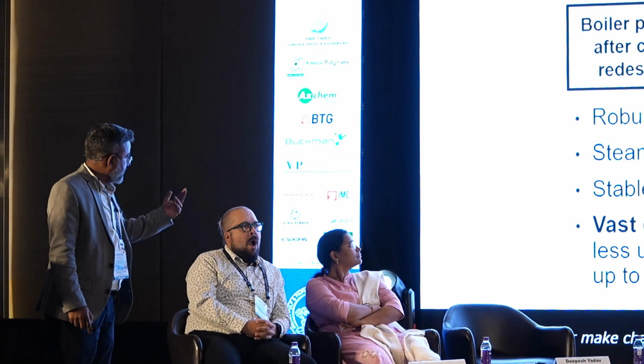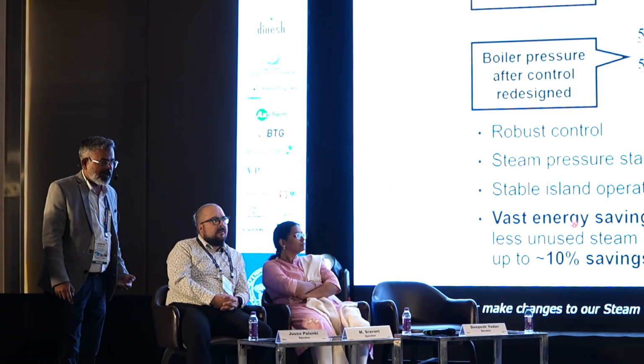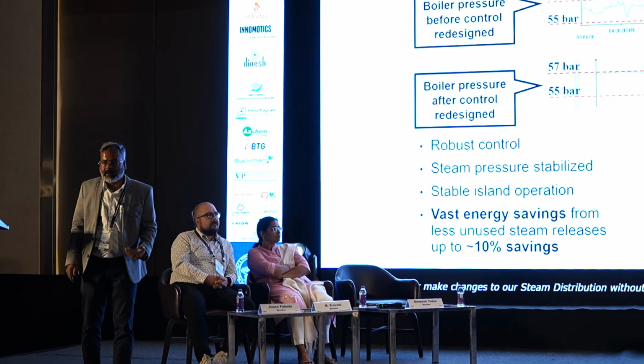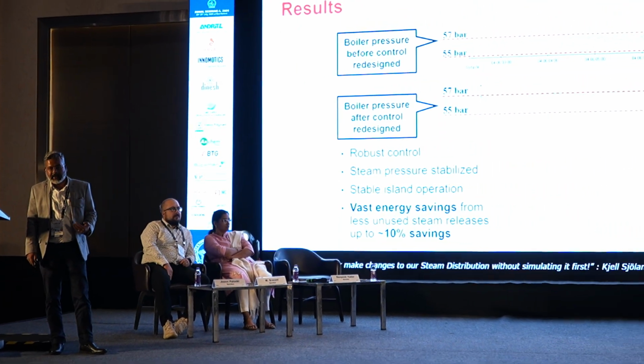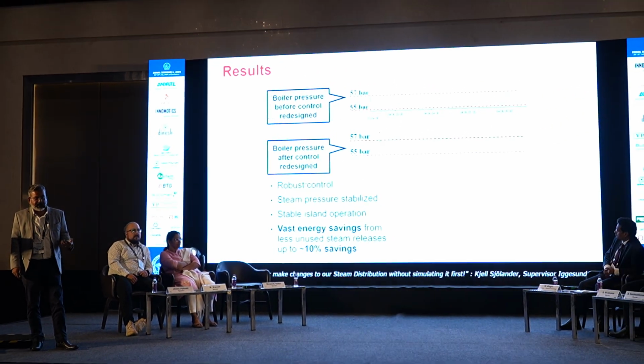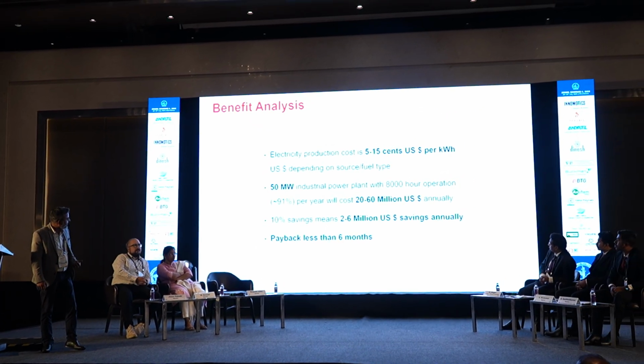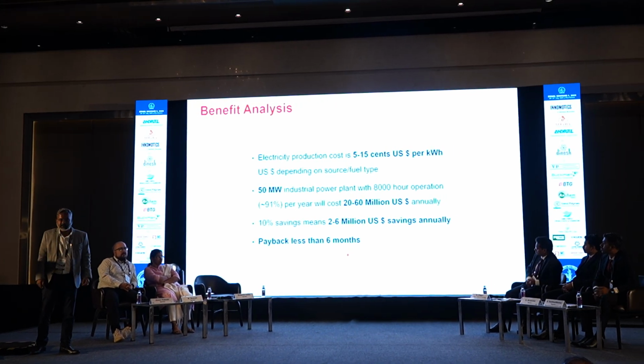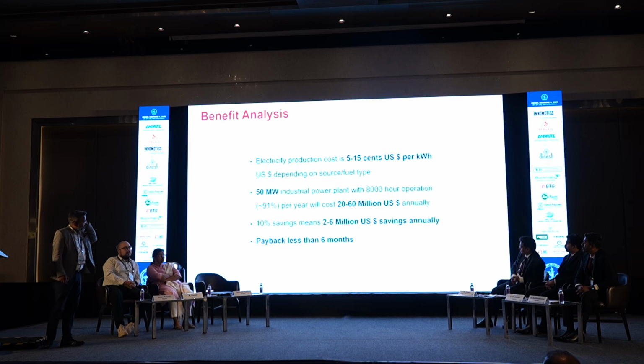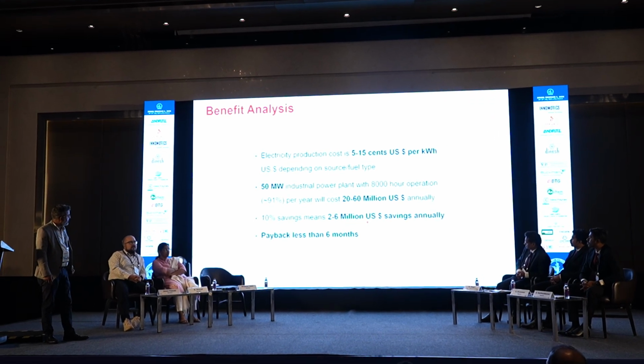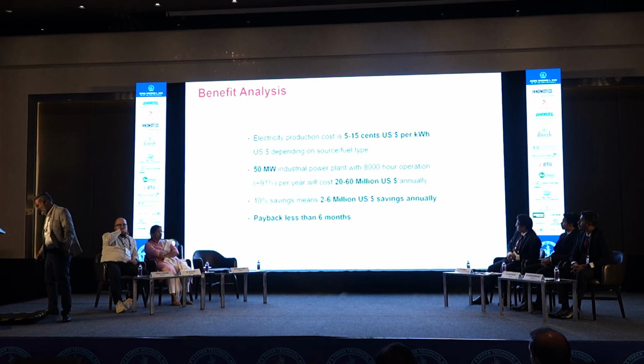Some of the benefits or results that we have seen here: the boiler pressure was initially oscillating around 55 to 57 bar, and after the control was redesigned, it was quite stable around 57 bar. So it's a robust control with steam pressure stabilized, stable island operation, and energy savings of around 10% that we have been able to achieve here with less venting of the steam. If we quantify it, it roughly turns out to be around $2 to $6 million in annual savings, depending upon the source or type of the fuel. And the payback period for this project was less than 6 months.